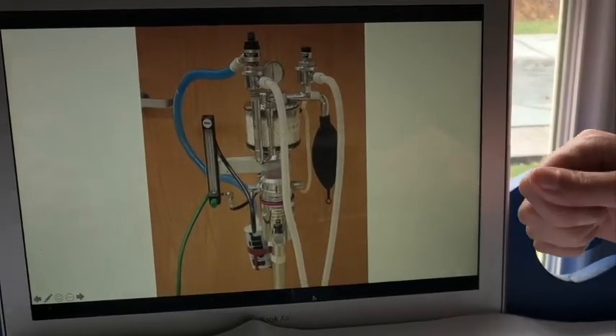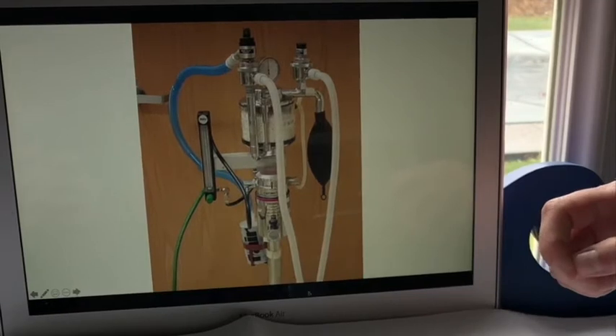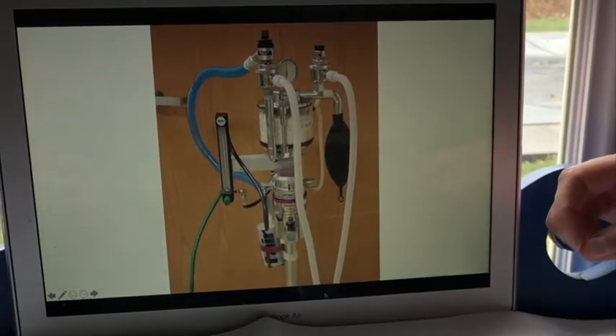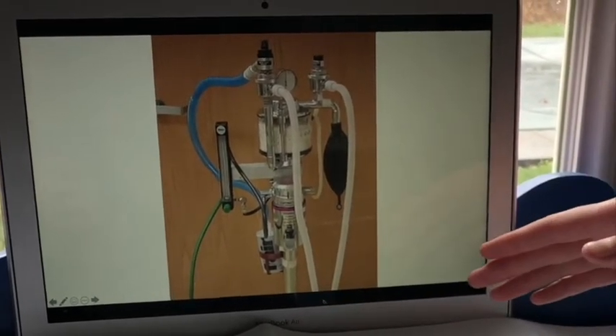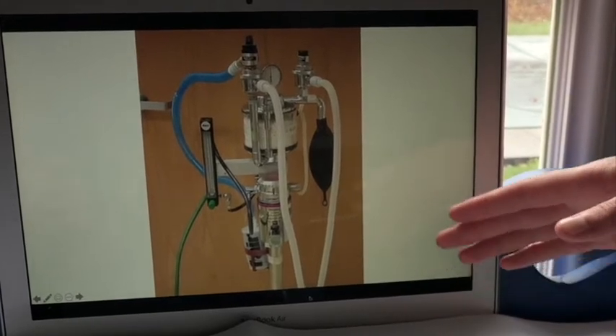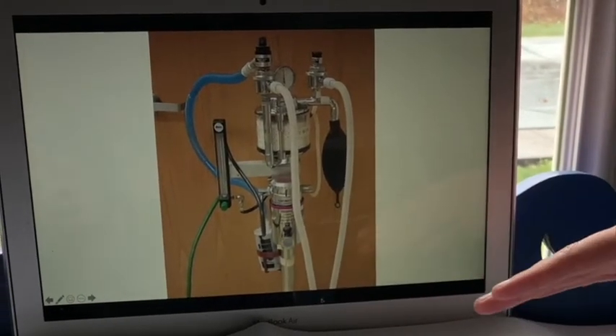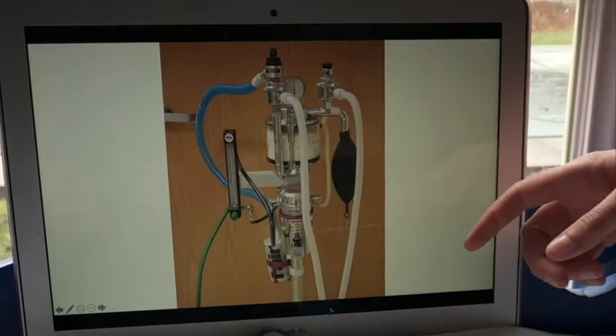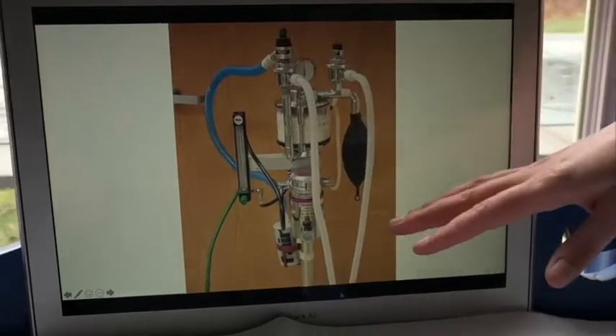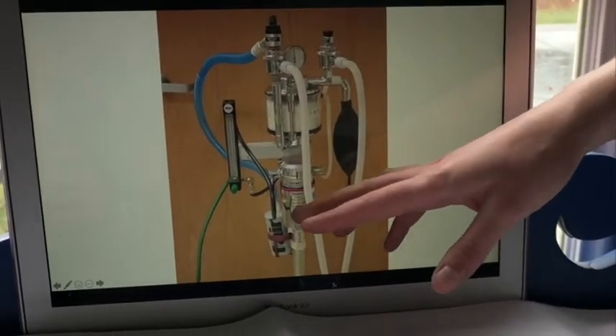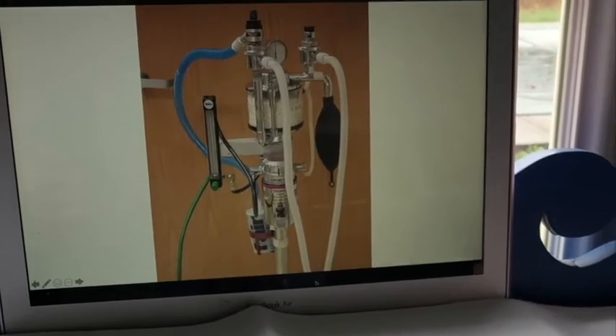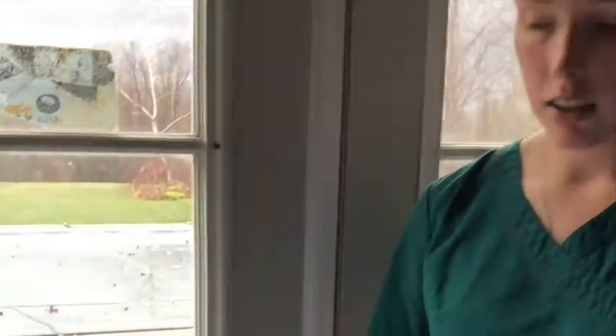Then the pressure should not decrease more than 10 centimeters of water within 30 seconds. So just watch that pressure manometer for 30 seconds and make sure it's staying steady and not excessively decreasing. And then we can open up our pop-off valve. The gas will go to the F air canister. And then our next step is to do the scavenger system test.